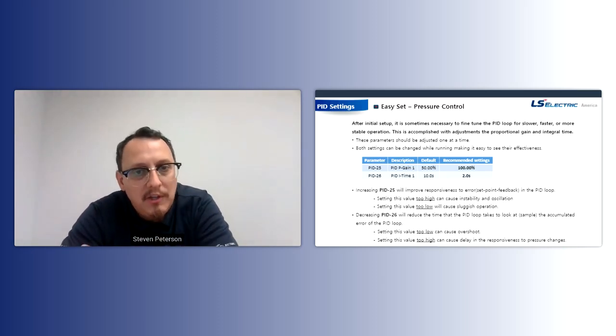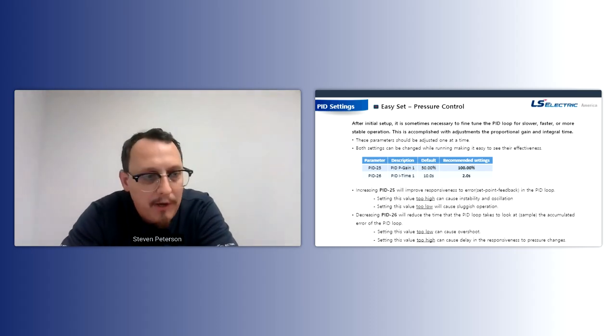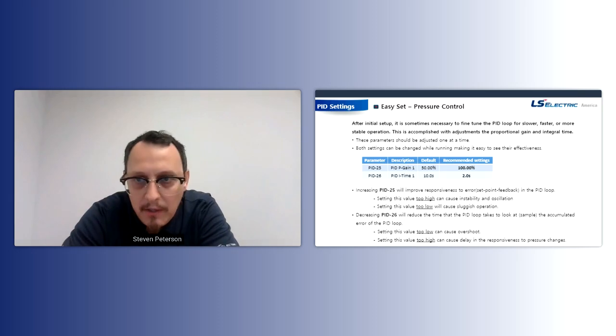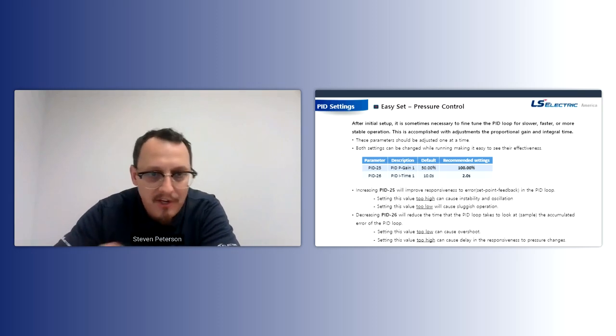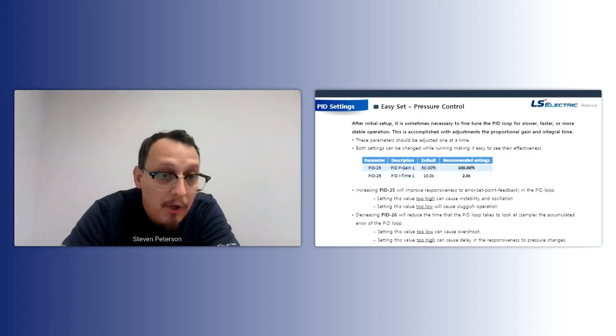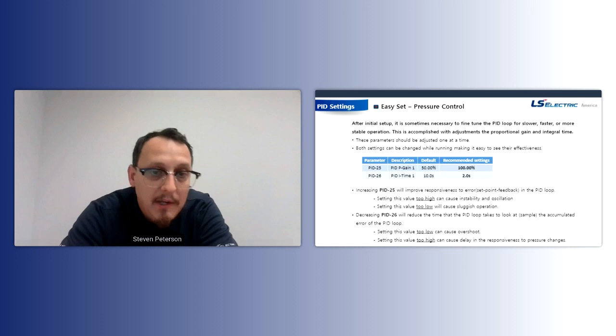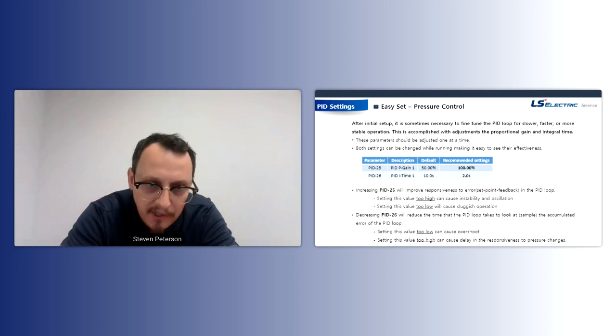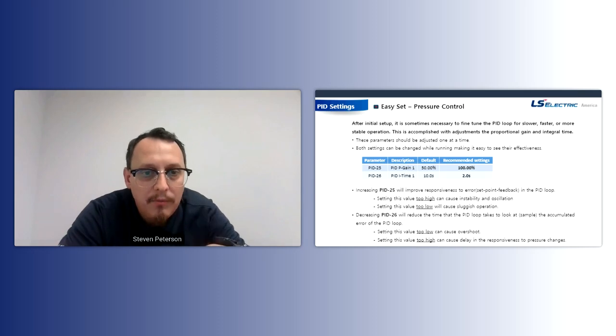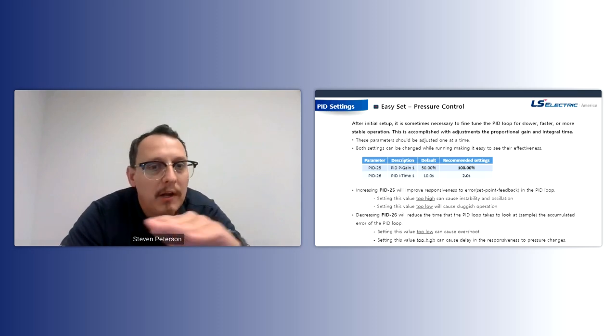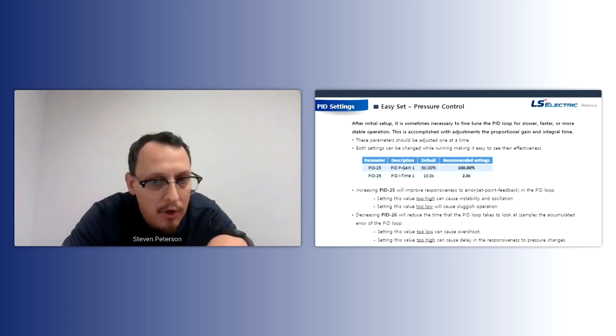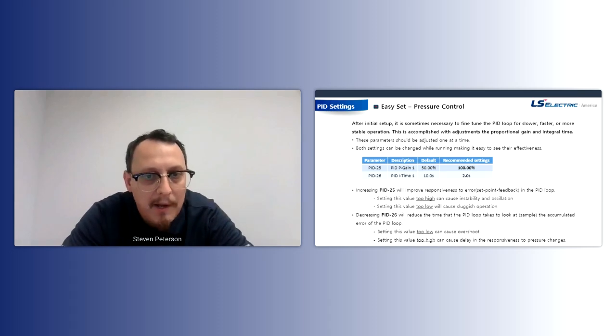I recommend adjusting these parameters one at a time. You could actually make changes to these parameters while the VFD is running, which is great. Sometimes you have to stop the drive, change your parameter, and run it, but on our VFD, you could change these on the fly. We do PID setups all day, and if anybody calls and says it's a little bit sluggish, the first thing we would do is adjust this P gain. It defaults to 50%, you could crank it up to 100%. I like the value of 200%. That makes it pretty responsive.